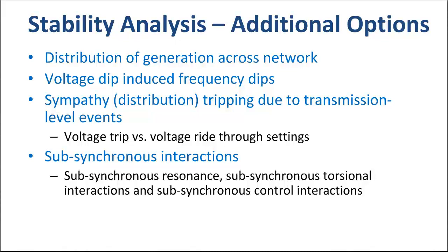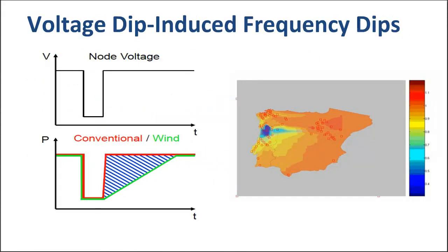I'm just going to focus on the second one briefly, voltage dip-induced frequency dips, and explain what that concept is. On the top trace, we're showing the nodal voltage, so a fault has been applied. On the bottom trace, we're showing the response in red of a conventional synchronous machine, and you can see that it reduces its output during the fault, but recovers quickly. The green trace is showing what a wind turbine might do, so it has a slower recovery. And the blue area is showing that there is going to be a lost energy area. So there's going to be a power imbalance due to the initial fault.